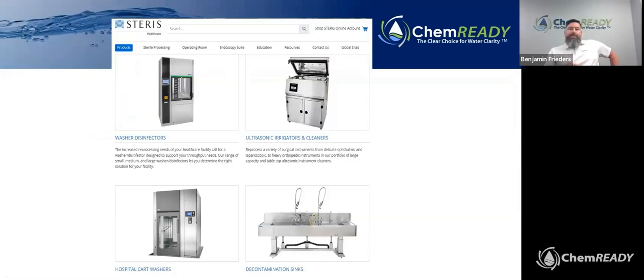Here are some pieces of equipment that you should be fairly familiar with if you are in SPDs or if you're in healthcare in general. So Steris is a common manufacturer. Obviously, there are multiple other manufacturers out there, Getinge being another one. These are the pieces of equipment that would require that critical water be delivered to these devices. So you have washer disinfectors, ultrasonic irrigators and cleaners, hospital cart washers, and decontamination sinks. So again, as the standard mentioned before, not each of these devices requires critical water to be delivered to them at each stage, but it's important to understand your equipment to know where it needs to be delivered.